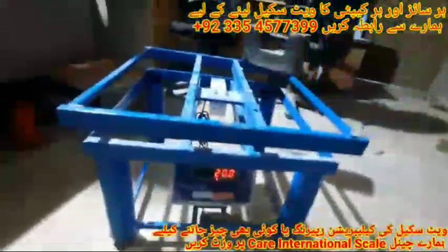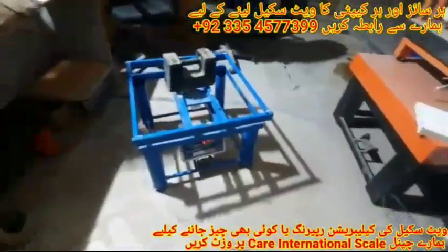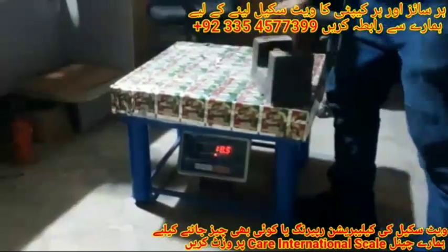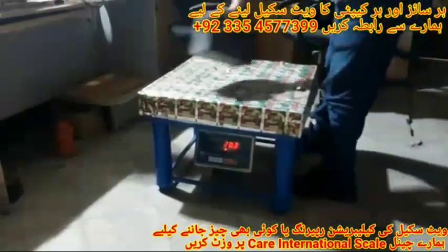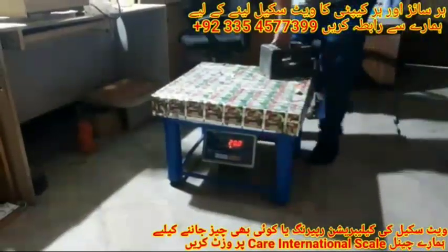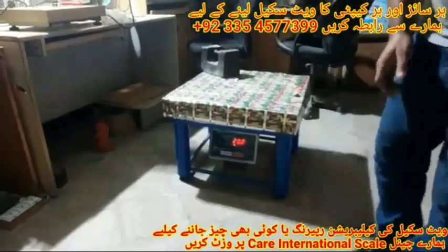Let me check the weight again. You can see it shows exactly 20 kg in all corners of the platform — first, second, third, and fourth. If we put it in the center of the platform it also shows 20 kg accurate weight. Now we put it on the scale and check: the weight shown in all corners is accurate and the same. First corner: 20 kg, second corner: 20 kg, third corner: 20 kg, fourth corner: 20 kg. Done.